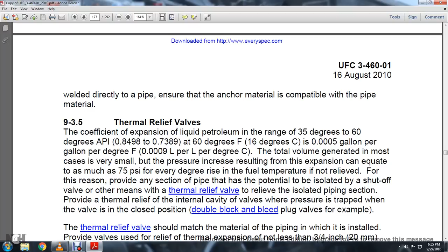Thermal relief valves should match the material of the piping. Valves used for relief of thermal expansion should be not less than 3/4 of an inch nominal pipe size. They should be provided with isolation ball valves with removable handles on the inlet and outlet. The set pressure of the relief valve will vary, but consider a set pressure of about 10% above the dead end head pressure of the pump. This should keep the valve from opening during normal fuel operations. Ensure the set point is within the design limitations of the piping.